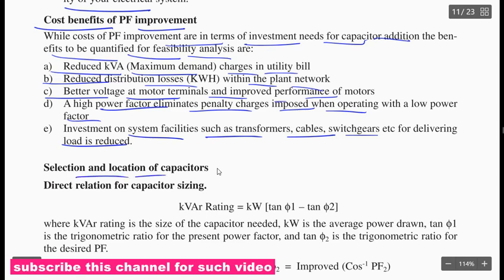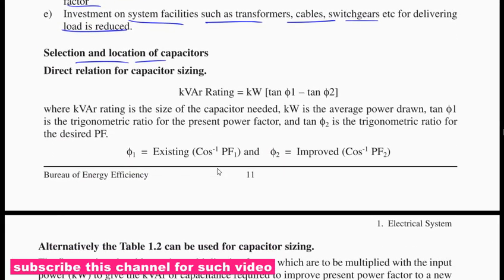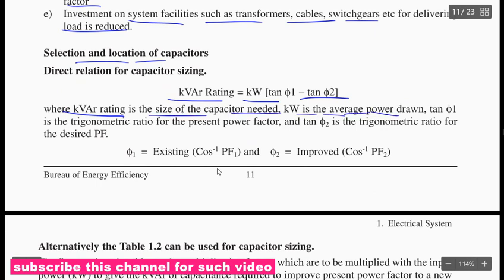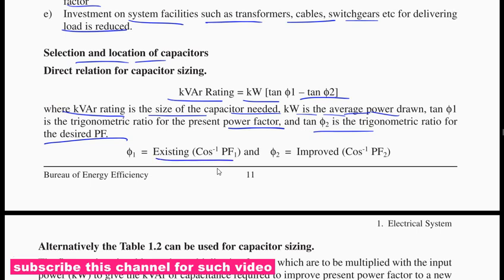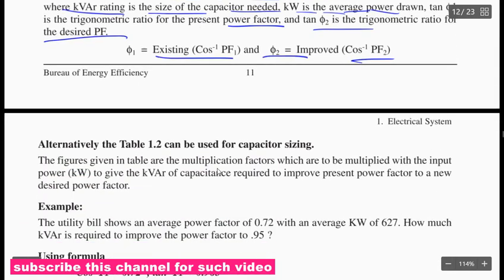Selection and location of capacitor. Direct relation for the capacitor sizing: kVAr rating equals kilowatt times (tan phi 1 minus tan phi 2), where kVAr rating is the size of capacitor needed, kilowatt is the average power drawn, tan phi 1 is the trigonometric ratio of the present power factor, and tan phi 2 is the trigonometric ratio for the desired power factor. So phi 1 is cos inverse of the existing power factor, and phi 2 is the improved power factor.